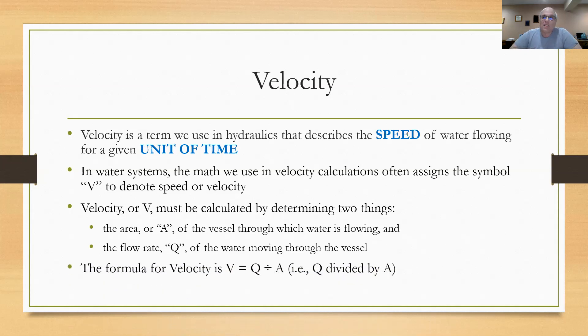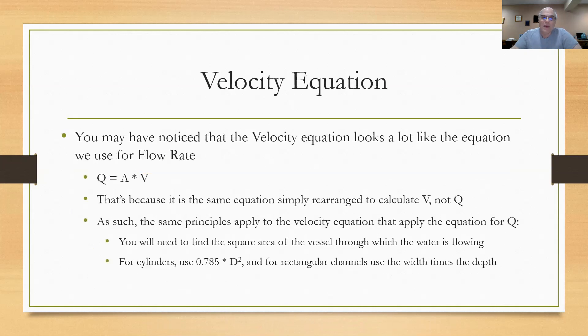The area, or A, of the vessel through which the water is flowing, and of course the flow rate, or Q. And we did that in a previous video. So to determine the speed at which water is moving through our systems from point A to point B, we need to know the size of the vessel, the pipe or tank it's flowing through, and the amount of water per unit of time. The formula for velocity then is V equals Q over A, or Q divided by A.